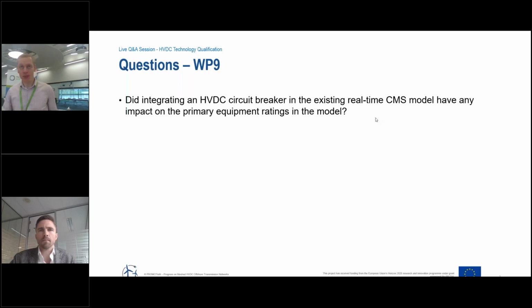I didn't do a full factory system test, so I've not checked every single element, but certainly I could still do the normal startup sequence, dispatch power to whatever level, and do a lot of the normal functions. And even with integrating the big inductor that's needed for the DC breaker, when it energized the cable, you could see it took a wee bit longer to energize, but it didn't seem to trip any of the other protections. So I hadn't broken the pre-insertion resistors or anything like that. So without doing a full redesign work, nothing obviously jumped out as a big issue for integrating a breaker in.